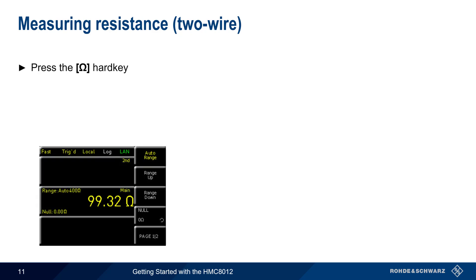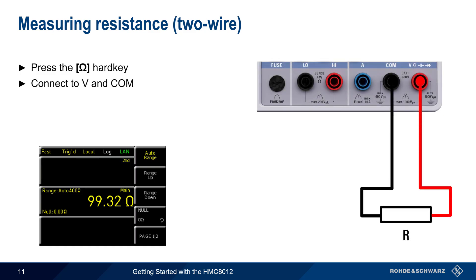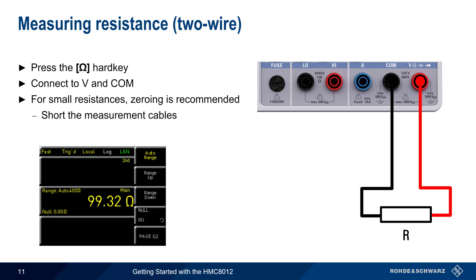Next let's look at resistance measurements, which are enabled by pressing the ohm hard key. Resistance is measured by connecting to the V and COM jacks, and the polarity of the cables is not important. Note that when measuring very small resistances, zeroing is recommended. Zeroing applies an offset correction to remove the effects of cables, contact resistance, etc. The zeroing process is performed by shorting the measurement cables or leads together, and then pressing the null hard key on the front of the HMC.